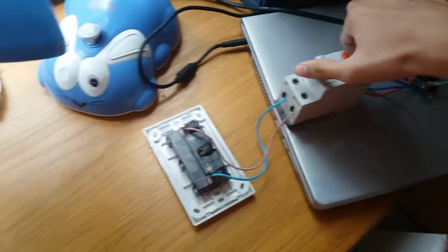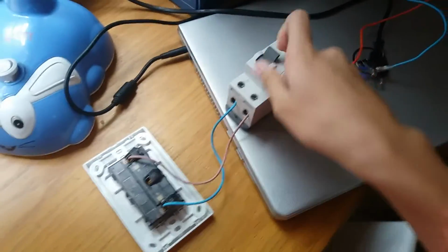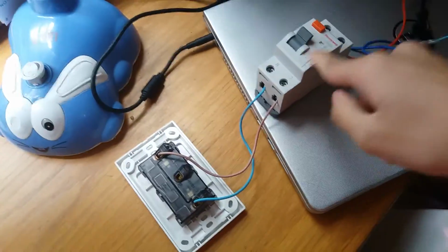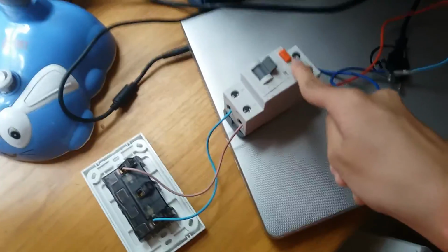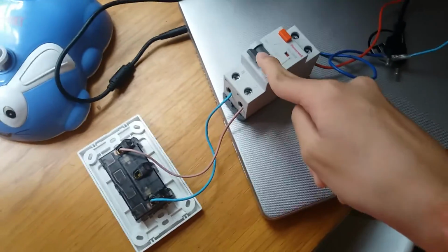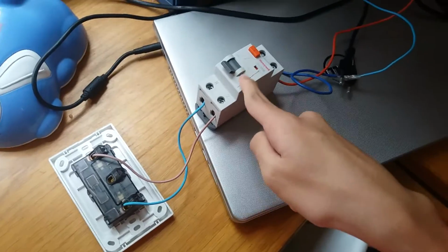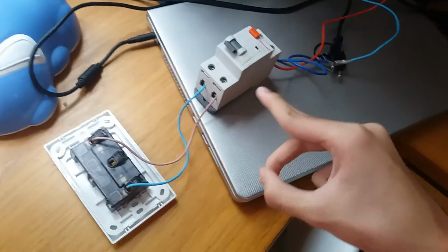We have three ways to test the breaker. The first way is to turn it on, then off, then on again, and we press the red button on top. You see the breaker immediately tripped. That means the breaker is still good, it still works well.